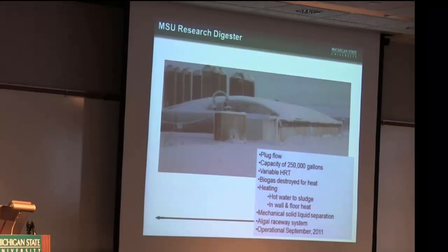And this was developed through a research project with Michigan Public Service Commission. And this is built for roughly a 100 to 200 cow dairy, which is the range of the average dairy farm in Michigan. And it's a relatively low-tech, low-cost digester that is effective at producing biogas, reducing odors. Doesn't generate a tremendous amount of gas. If we put an electrical generator on this system, we can support about 70 kW of electrical production.